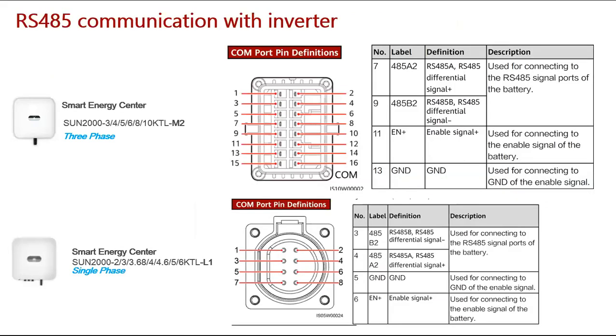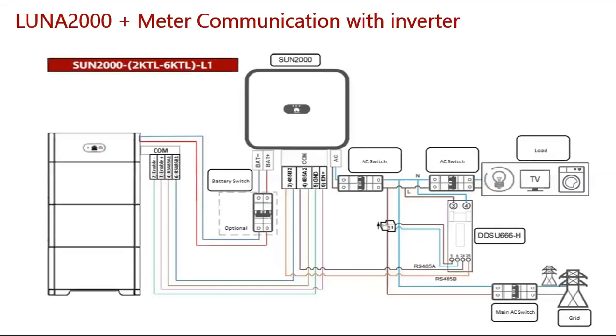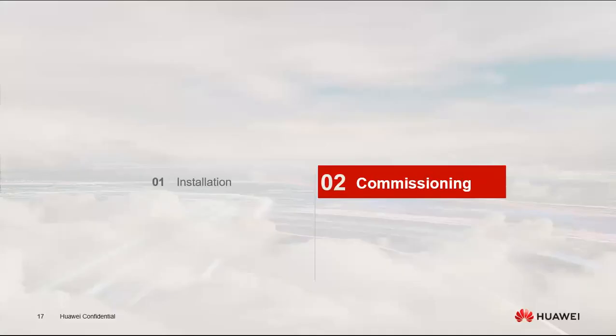Going back to that slide on RS485 communication with the inverter: for the three-phase inverter, you will use only 4 pins, which are 7, 9, 11, and 13. For the single phase, you will use 3, 4, 5, and 6. So only 4 pins will be used, don't confuse yourself or the installers with the number of ports or pins available on the communication connectors for that inverter. Only 4 pins are used to communicate with that inverter and with the Luna battery system.